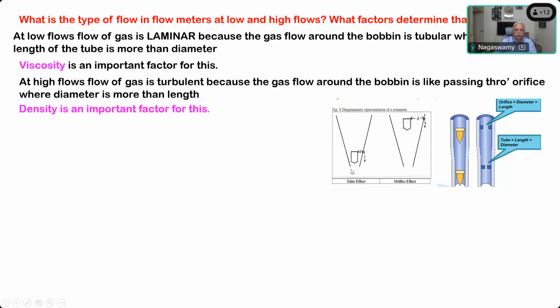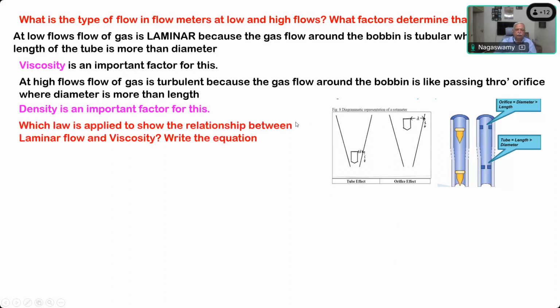When the gas is at a low flow and the bobbin is at the bottom of the flow meter tube, you have a tube effect where the length is more than the diameter. Okay? Whereas at high flow, it behaves like an orifice where the diameter is more than the length. So this is the explanation for it.